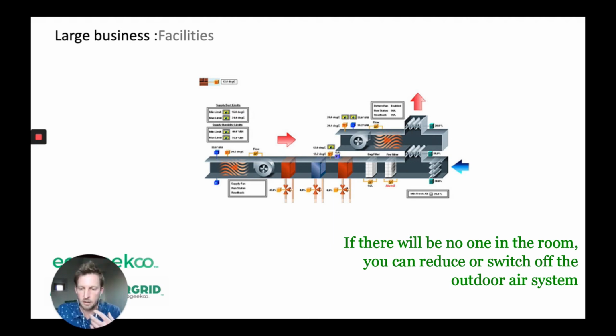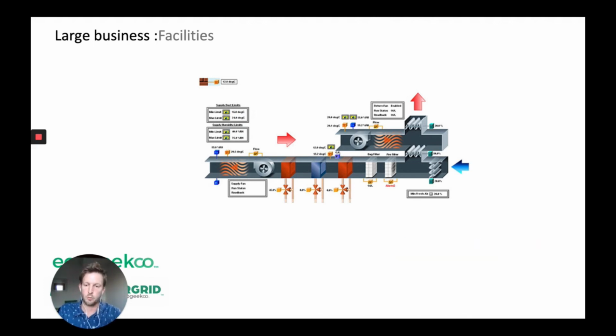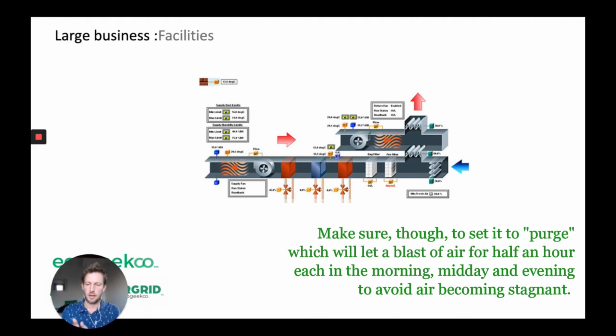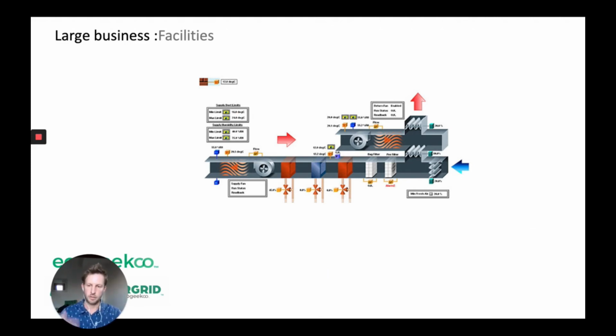So you can reduce or switch off the outdoor air system, but I strongly advise having what's called a purge, where you have it set to come on, say, for a half hour or an hour blast in the morning, another blast during midday, and another blast in the evening. So you're just turning over the air in the building, but you're not providing it continually stocked with heated or cooled fresh air, which is done by very, very big fans that cost a lot to run. So that is an area where you can make another huge saving on your energy bill whilst your building is in effective lockdown. So a good one to do. Lots of energy use there.